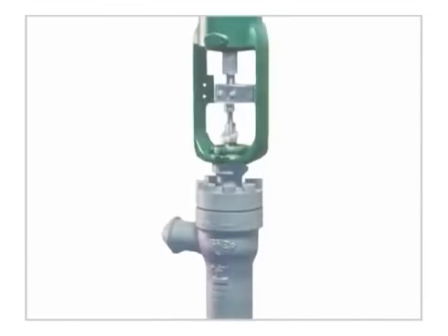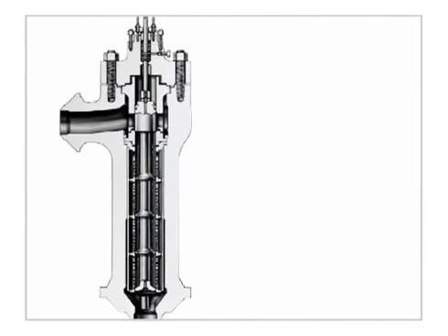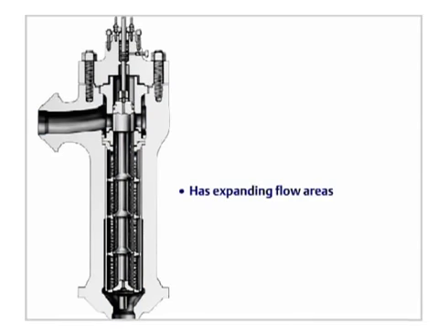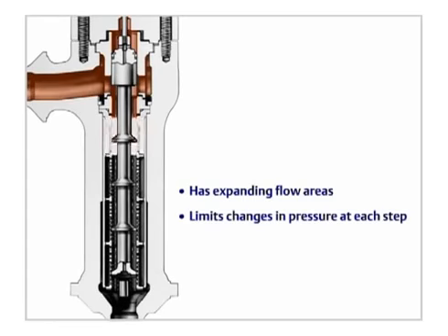In addition, the Cavitrol IV valve trim has expanding flow areas that decrease pressure as the fluid flows through. Limits changes in pressure at each step to prevent fluid from reaching the vaporization point. And prevents leakage.